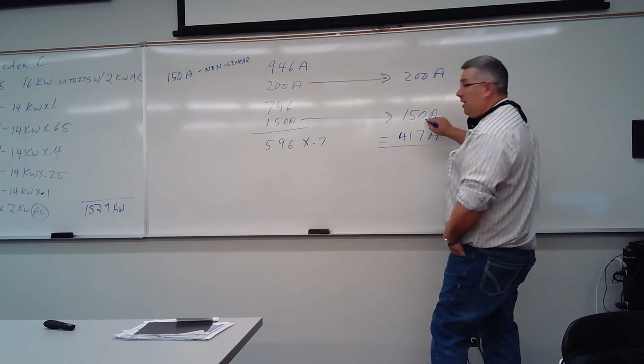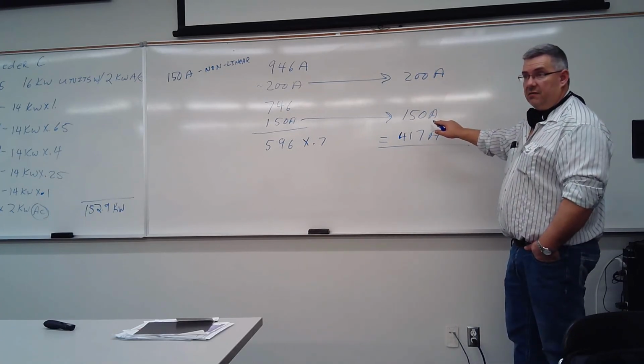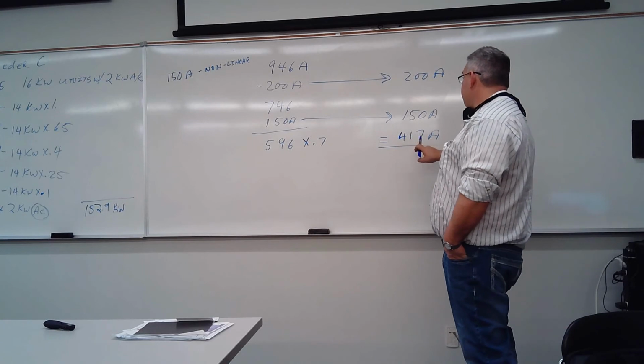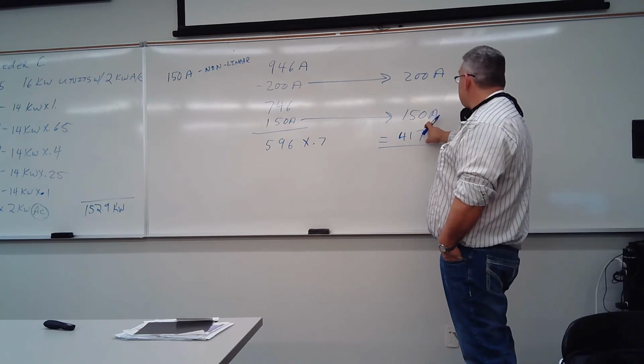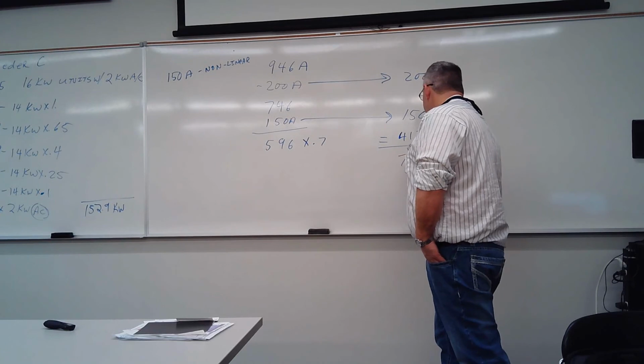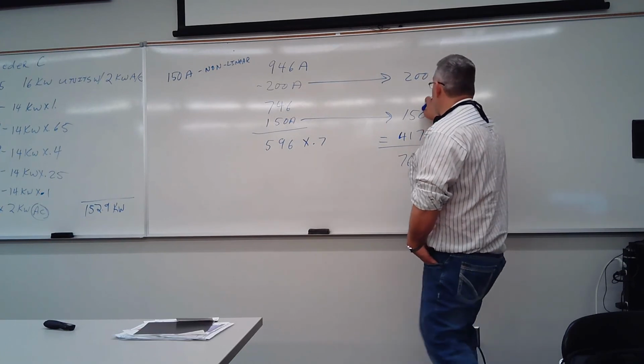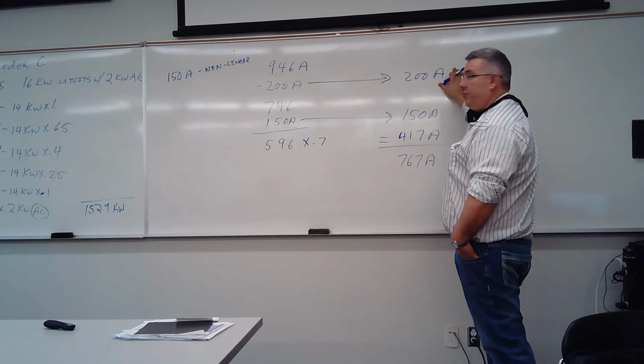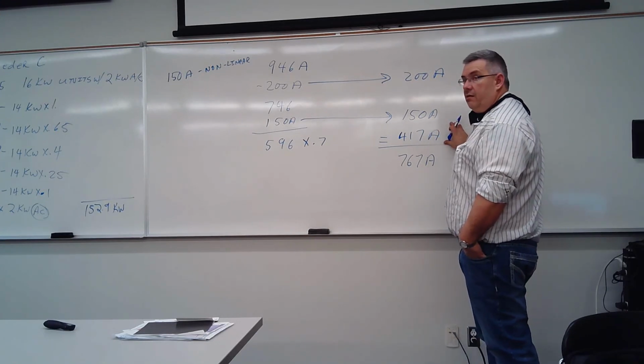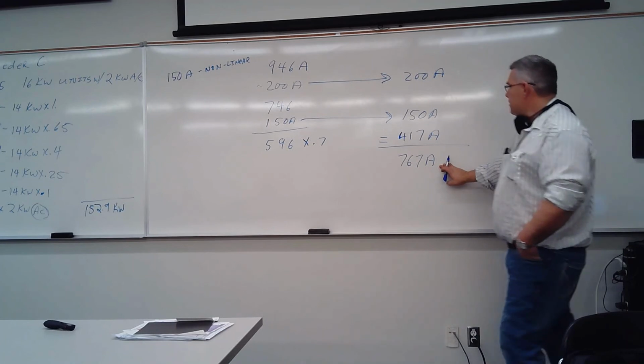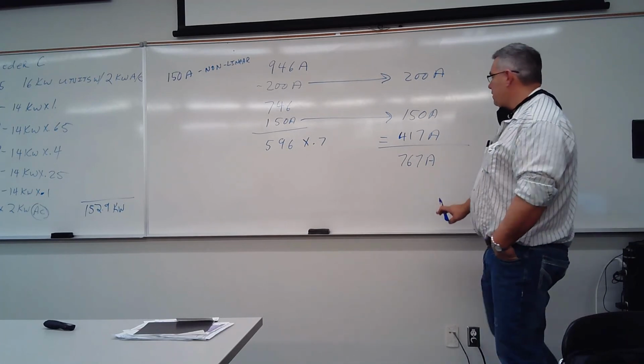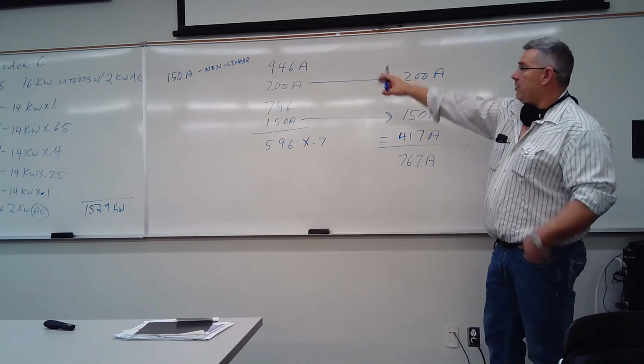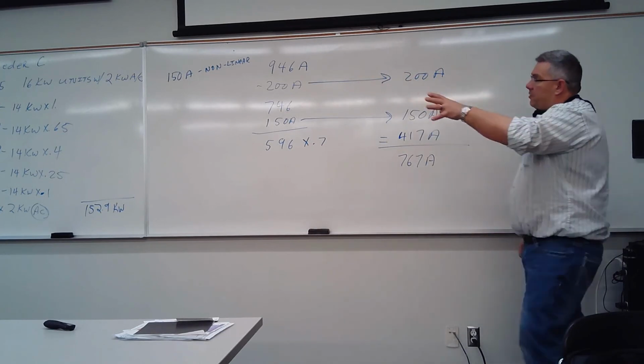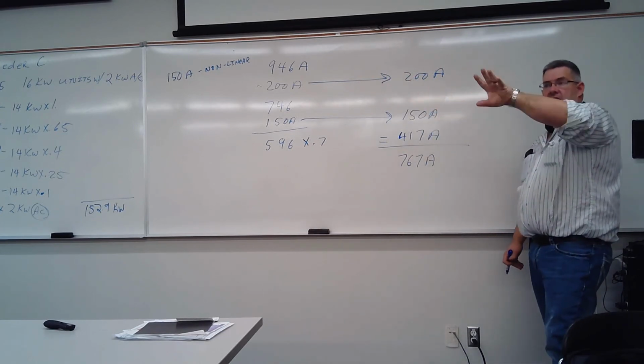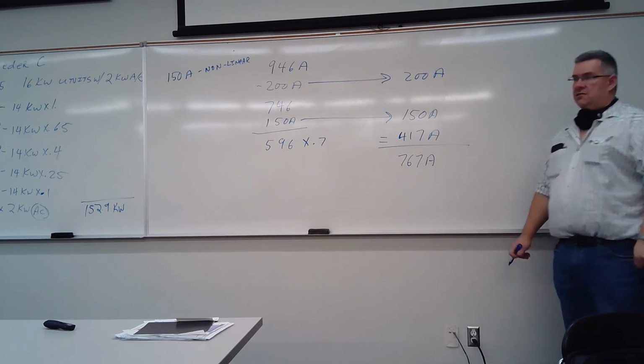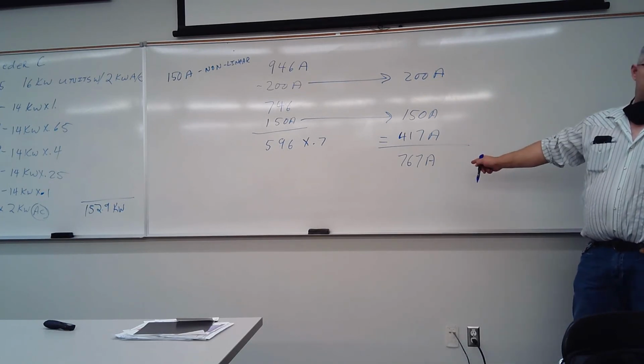And then we add back in these things we took out because we had to run them at 100%. So now 417 plus 150 is 567. Do we add that 200 again too? Yes, you add these things that you took out because you're not allowed to reduce them back into that. This number should be 767, right? Yeah. So we would actually pull 946 amp phase conductors and 767 amp neutral conductors to that service.